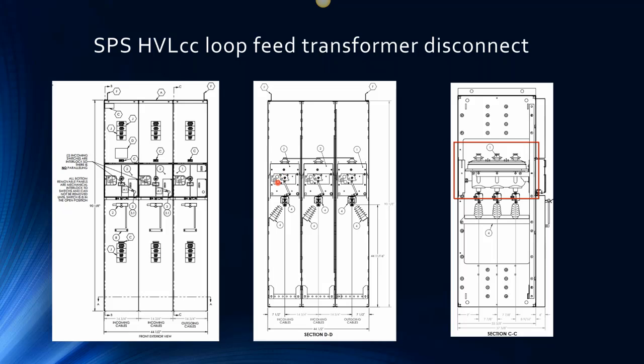So we have visible confirmation of blade disconnect and visible confirmation of grounding. And that leads to the last point here, which is that this can be ordered as a 3-position switch: closed, open, and grounded. So an integrated arc-safe grounding switch, so that the mechanism itself is arc-safe. It can be switched up from the outside, enclosed, energized, without any arc-rated PPE requirements, which of course is a maintenance advantage in many situations.